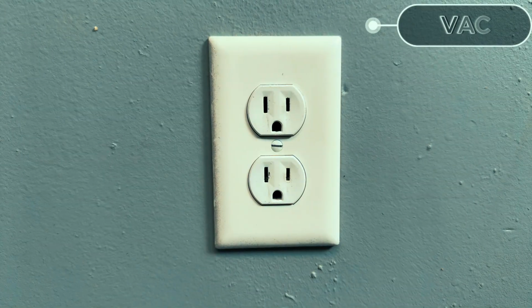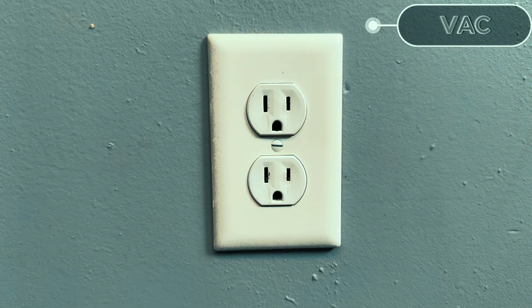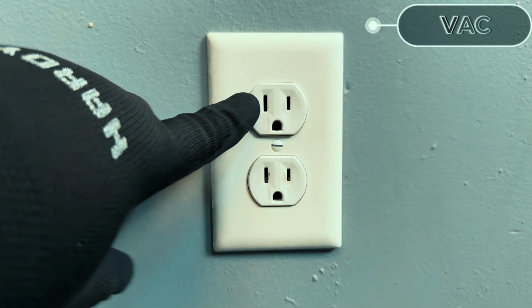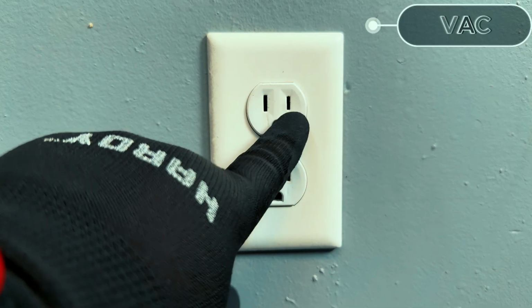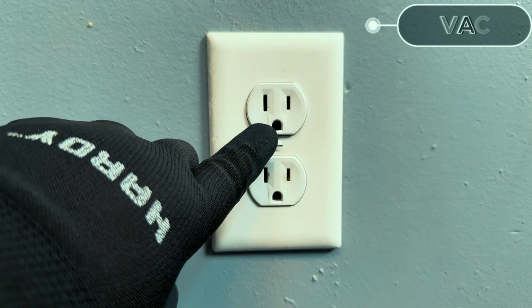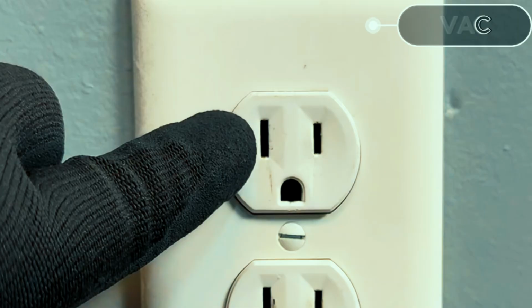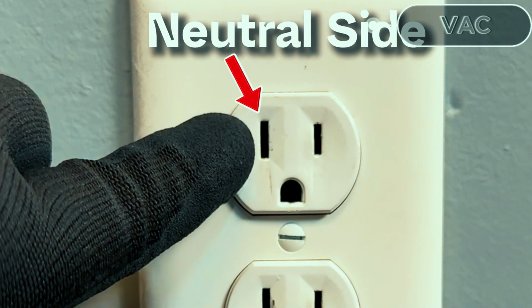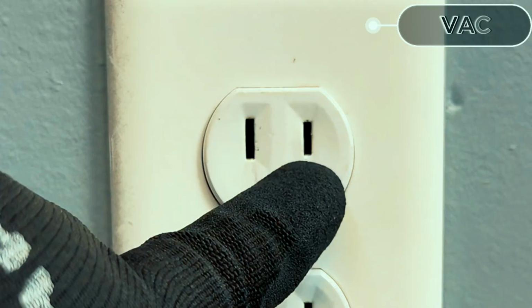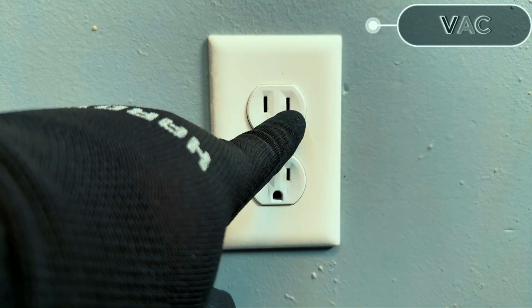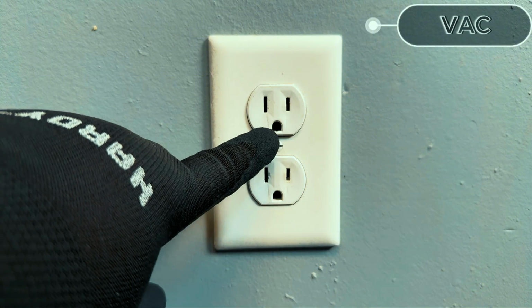So we're here at our outlet, and a few things that we have to point out here, and that's going to be what is your common side, your neutral side, and then your positive or line side, your hot side. So all outlets, you will see that they'll have a larger slot and a smaller slot. And of course, you'll have the little half circle here at the bottom. The larger slot, that's going to be your common, your neutral side of the outlet. The smaller side, that's going to be your hot side. That's going to be where the line power is. And of course, this bottom one, that's going to be your ground. So let's show you how to test that.